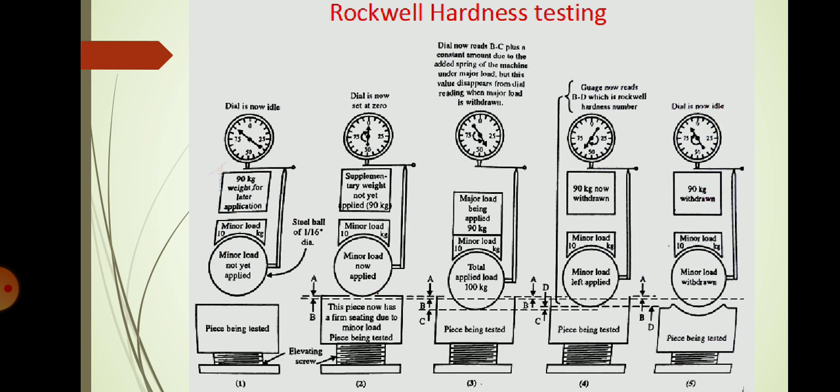So that is the depth gone inside the specimen in the first step. In the second step, after that, we are applying the major load. Major load of nearly 90 kg is applied. This application of load is dependent on which scale you are using.